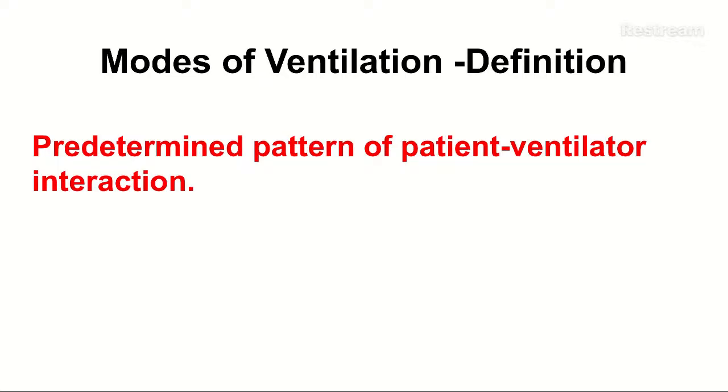All breaths are not equal, all modes are not equal, they are different in a way. How the flow will be delivered, how the ventilator will cycle to expiration, how it starts the breath. So to understand the ventilator, we need to know three things, that is trigger, target, and cycling.